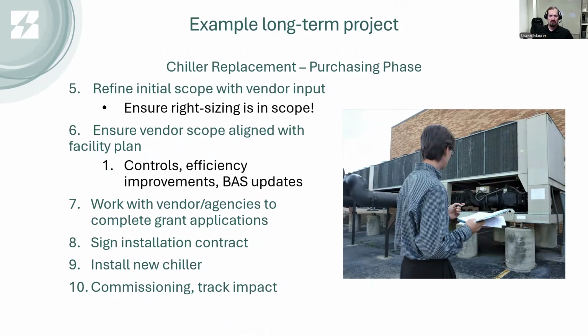This is where you really want to make sure they are right sizing the equipment, not just replacing it with the same size piece of equipment. Loads change over time in buildings, so particularly with cooling equipment, if it's oversized you'll get humidity control problems or equipment performance problems as the system cycles on and off. Right sizing should be in the scope - if it's not a line item in the scope of work, it should be added.